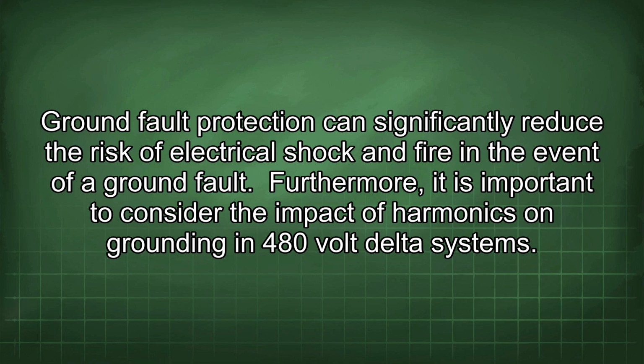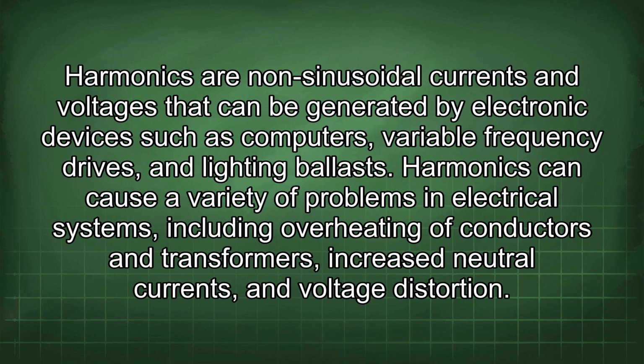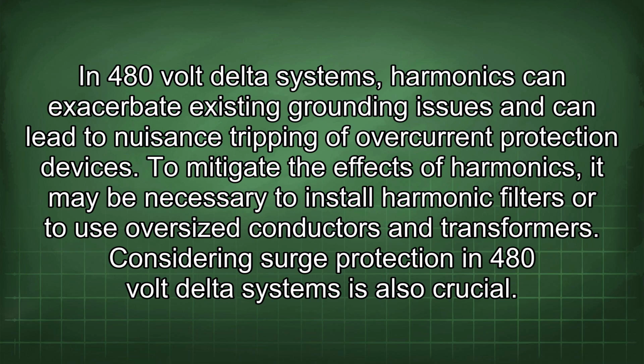Furthermore, it is important to consider the impact of harmonics on grounding in 480-volt delta systems. Harmonics are non-sinusoidal currents and voltages that can be generated by electronic devices such as computers, variable frequency drives, and lighting ballasts. Harmonics can cause a variety of problems in electrical systems, including overheating of conductors and transformers, increased neutral currents, and voltage distortion. In 480-volt delta systems, harmonics can exacerbate existing grounding issues and can lead to nuisance tripping of overcurrent protection devices. To mitigate the effects of harmonics, it may be necessary to install harmonic filters or to use oversized conductors and transformers.